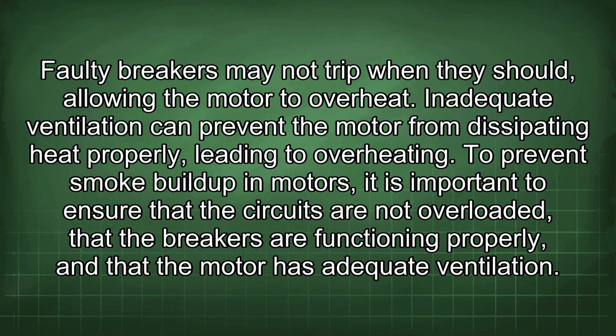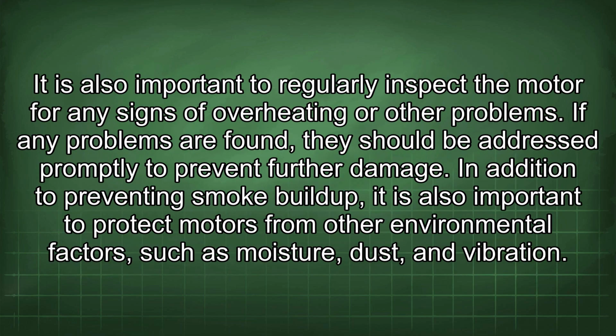Inadequate ventilation can prevent the motor from dissipating heat properly, leading to overheating. To prevent smoke buildup in motors, it is important to ensure that the circuits are not overloaded, that the breakers are functioning properly, and that the motor has adequate ventilation. It is also important to regularly inspect the motor for any signs of overheating or other problems. If any problems are found, they should be addressed promptly to prevent further damage.